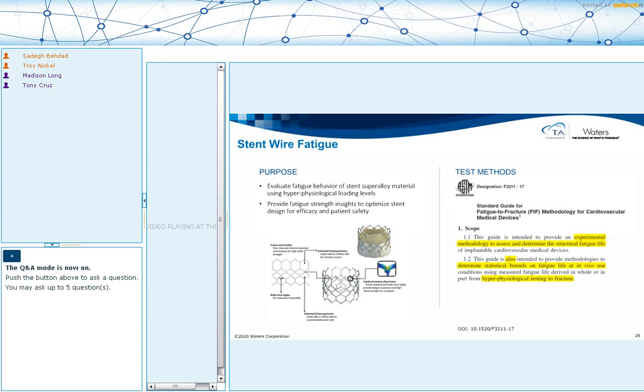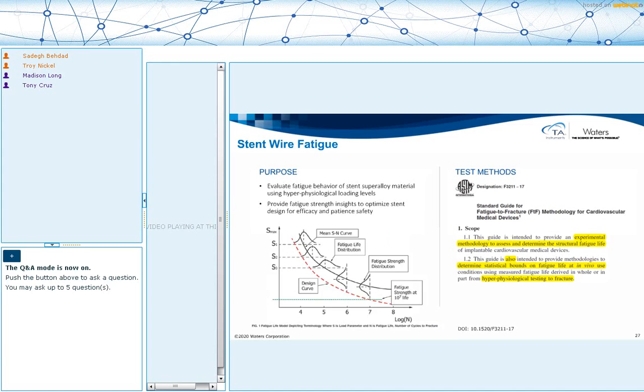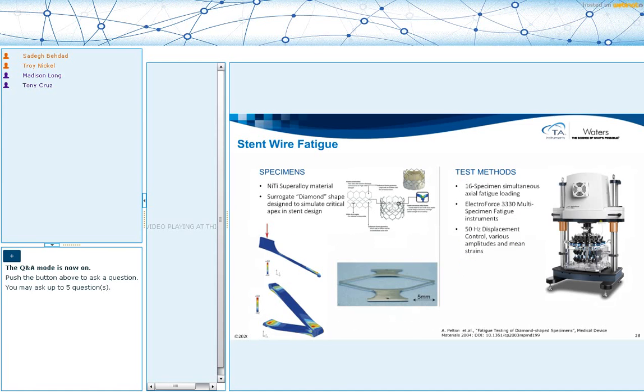When we are discussing fatigue behavior of the material, there are two paradigms. One is fatigue to failure, meaning that you will test your material until it breaks, and the other would be fatigue to success, meaning that we only test to a number of cycles to show that this material can withstand that many cycles. Usually, the first one, fatigue to failure, is used to establish design curves for the second one, fatigue to success. And it's important to measure a statistically valid number of samples to do that. And we have an instrument, we call it a multi-specimen fatigue. It allows you to apply the same deformation to 16 samples simultaneously and then measure their behavior.